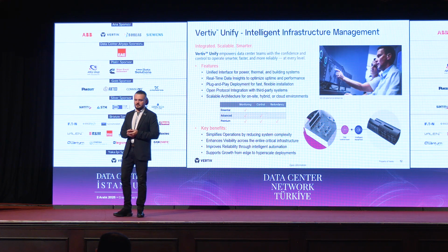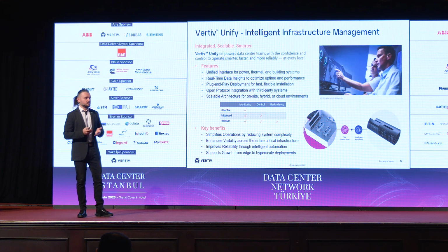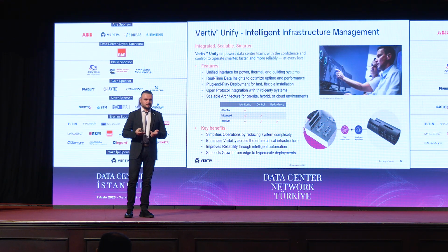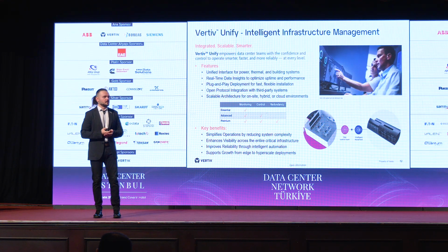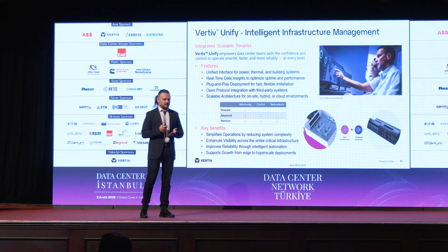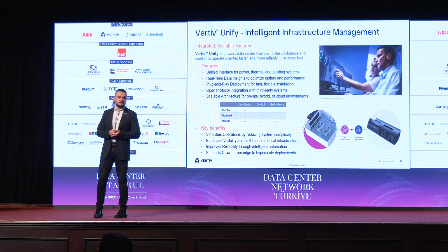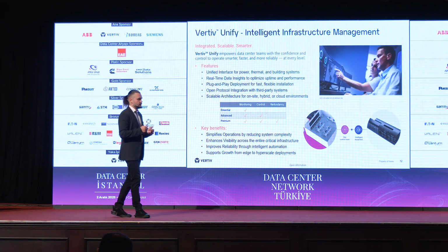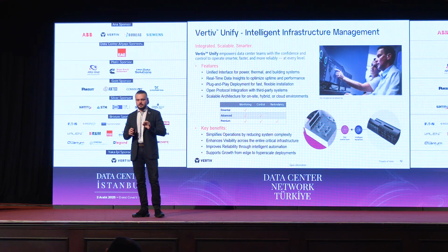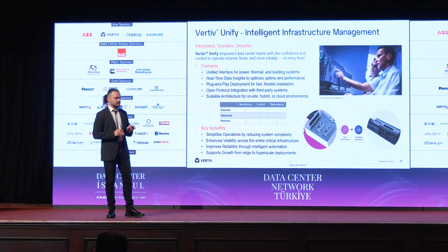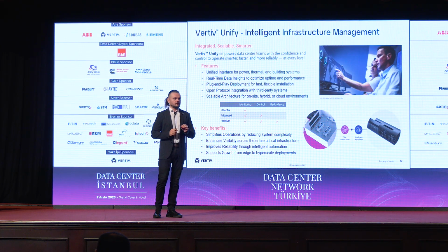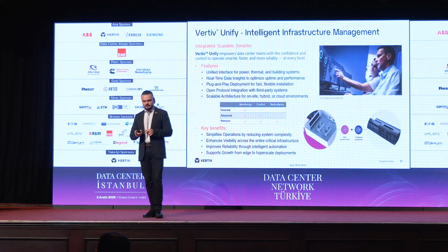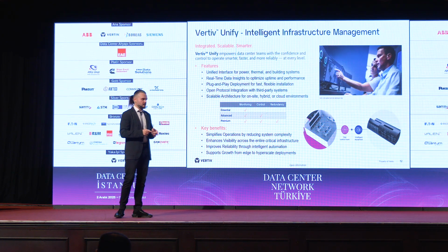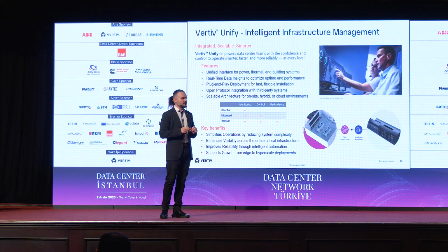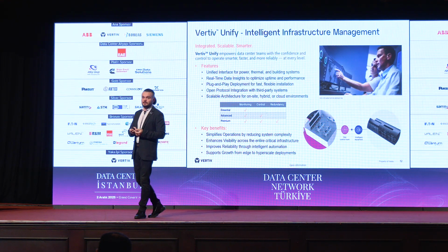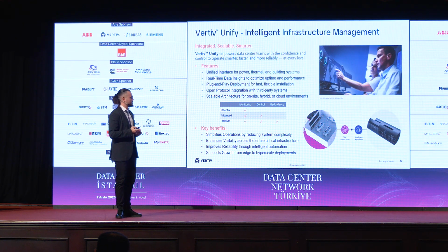So the SCADA system needs to have a special algorithm, not only to warn the dispatchers and the service personnel that something is wrong, but it really needs to be proactive. And we are combining it with a leak detection system, with valves that operate on the secondary fluid network. Just a simple example: if we have a leakage of the secondary fluid network near some server rack, we initiate the software shutdown of this server rack, and only after the system is sure that the server is shut down do we close the valves. Otherwise, again, the server can overheat and it can cause problems and even damage to the equipment.